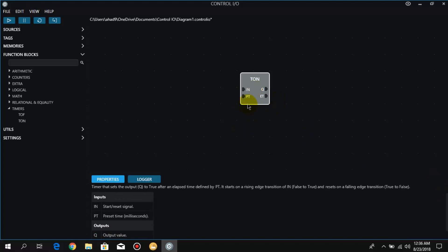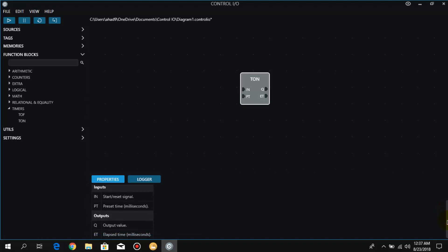The input IN is the start or reset signal — we have to give a signal to the timer in order to turn it on. We have PT which stands for preset time, that is how much time we set in milliseconds for the timer to turn on. ET is the elapsed time output shown as an integer, and Q is the output signal received after the particular time is achieved.